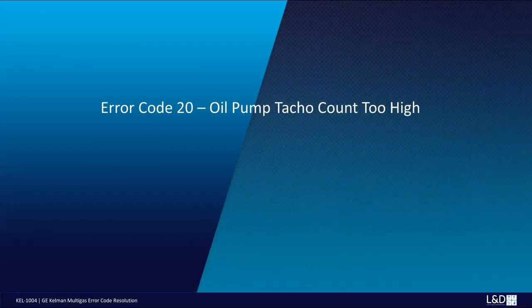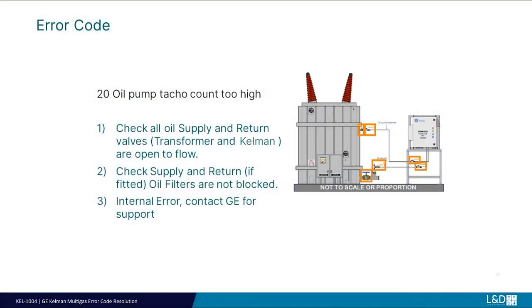Error code 20: Oil pump tacho count too high. Check all inline transformer and Kelman oil supply and return valves are fully open to flow. Check supply and return oil filters are unblocked if fitted. Check for any oil pipe damage.